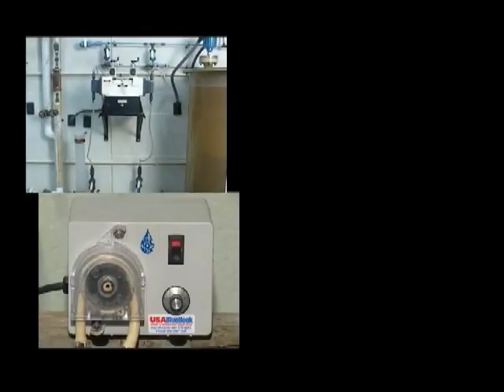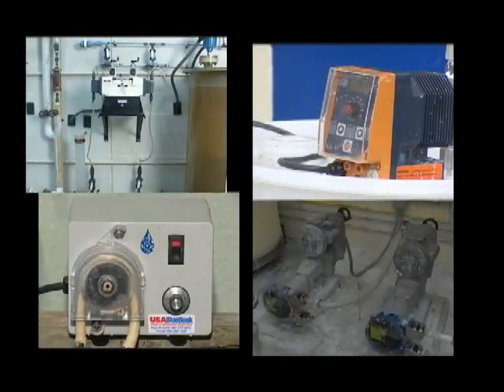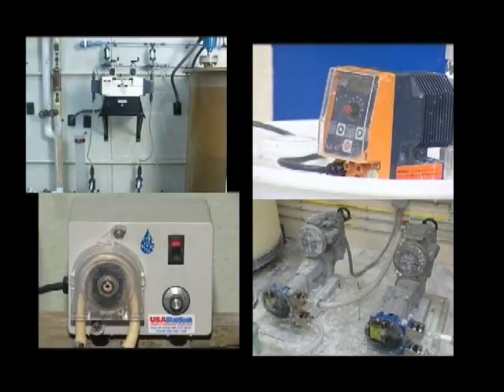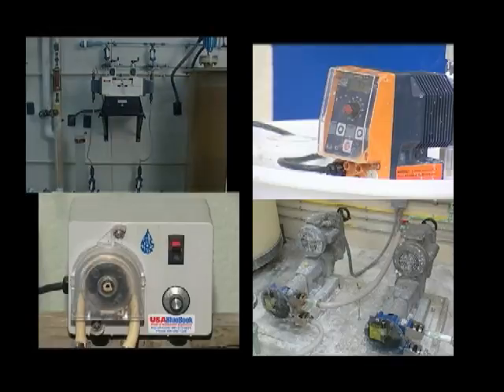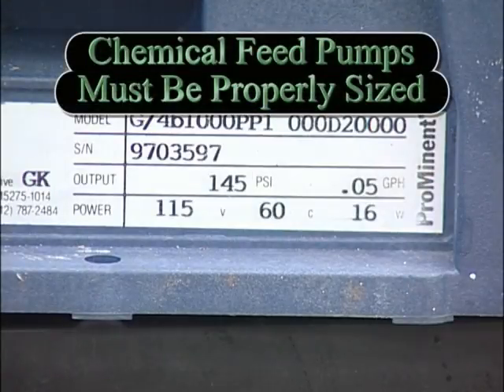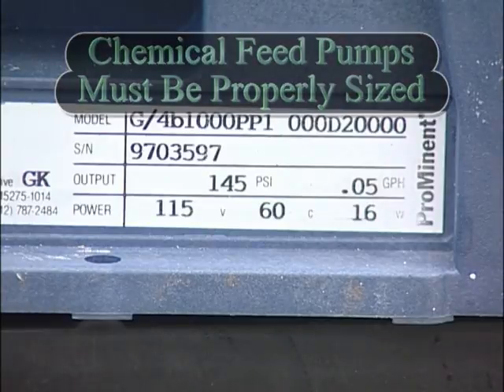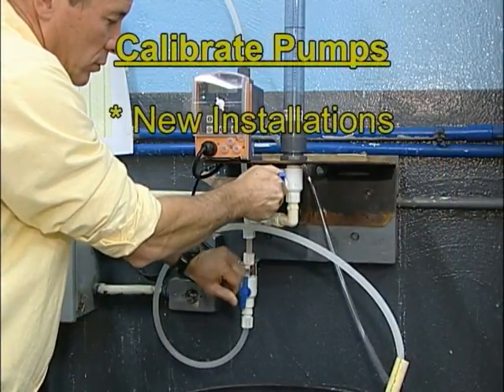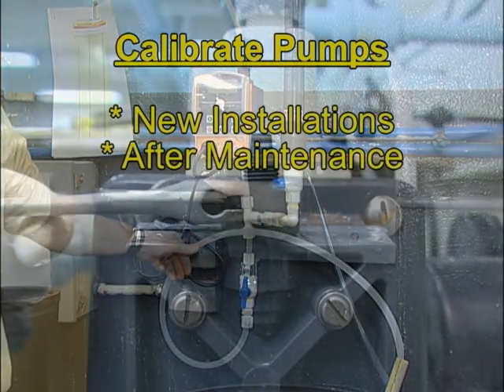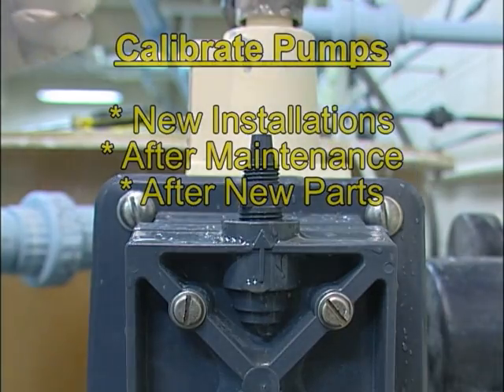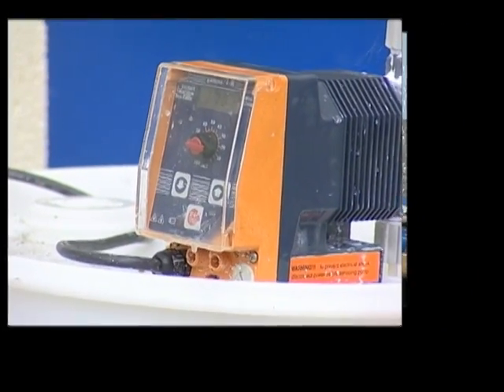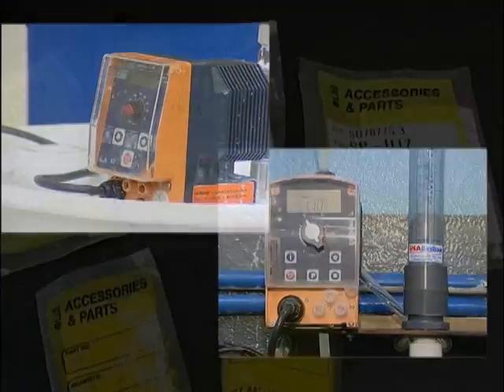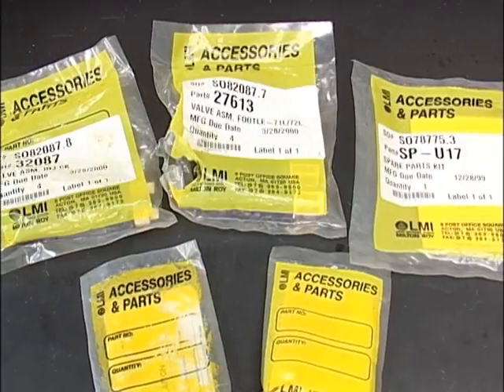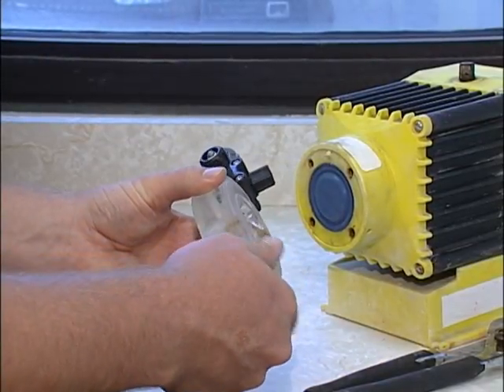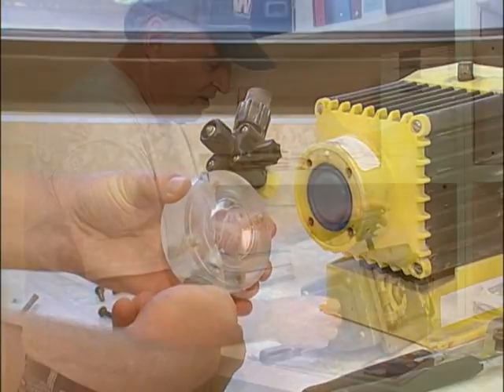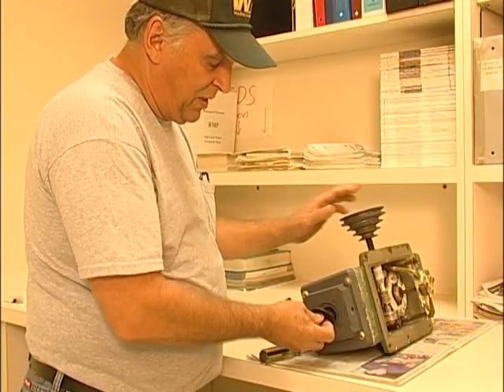There are a variety of chemical feed pumps and pump types to choose from. The operator should be careful to select the pump that will deliver the chemical accurately and consistently. Sizing the pump correctly is critical to the proper operation of a water treatment plant. All pumps should be calibrated when they are first put online and after any maintenance is done or parts have been replaced. Choosing similar pumps in terms of manufacturer and size when possible will lower the parts inventory required for uninterrupted operation. An ongoing operation and maintenance program is essential for chemical feed pumps as well as the other types of pumps used in water treatment.